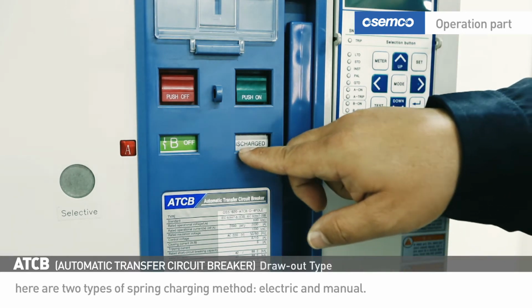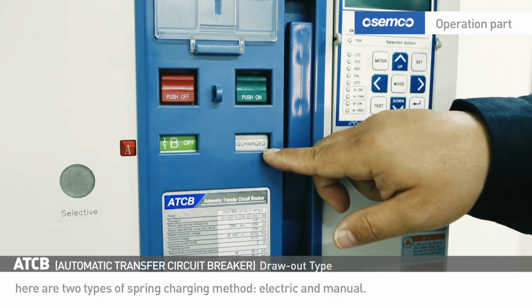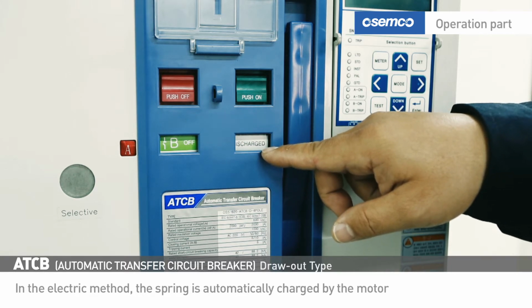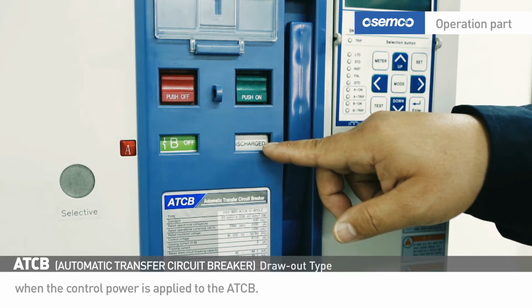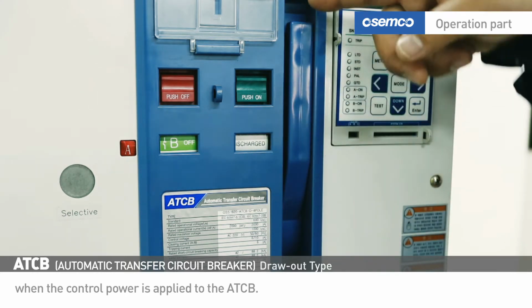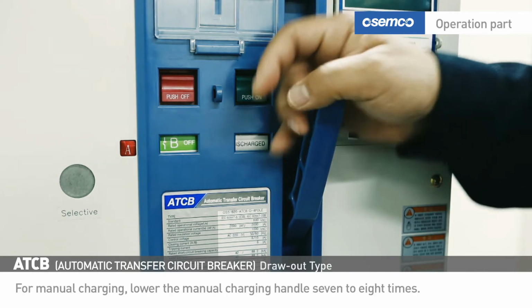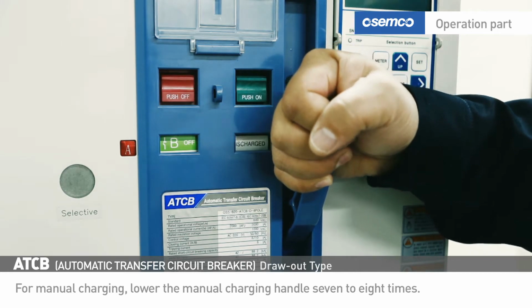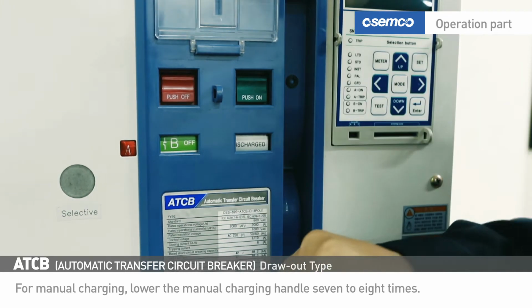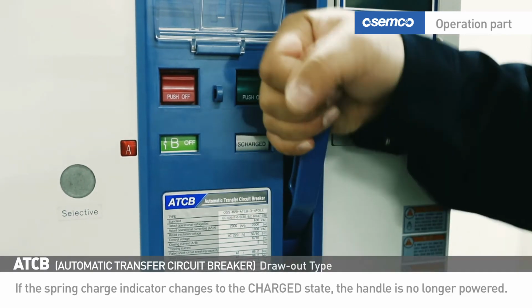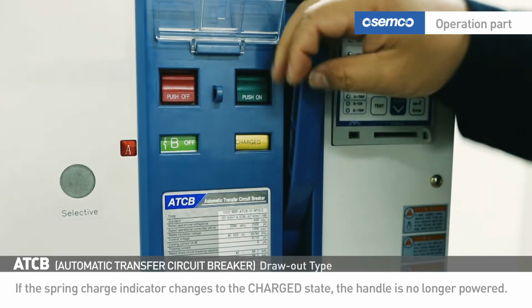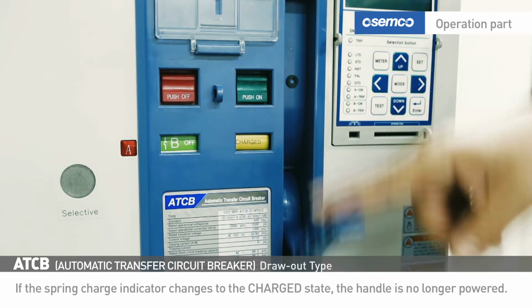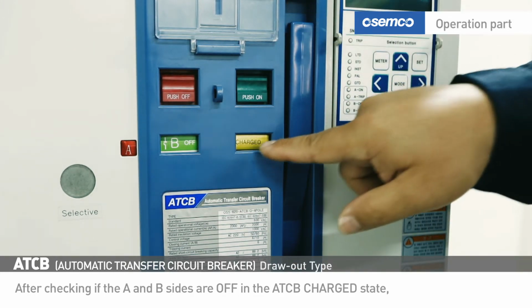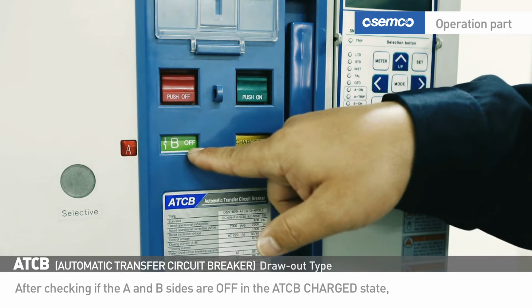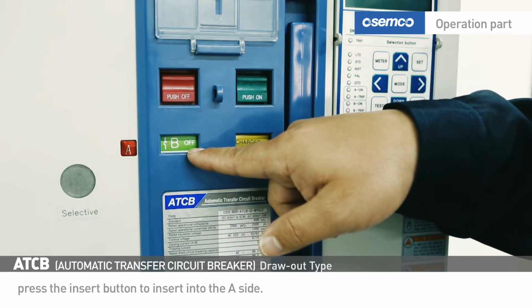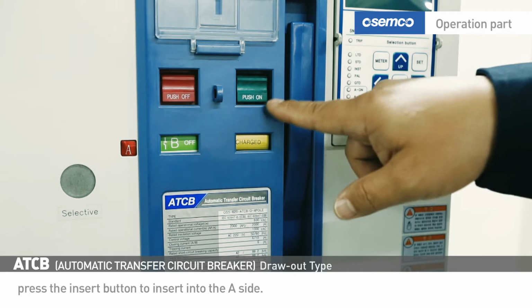There are two types of spring charging method, electric and manual. In the electric method, the spring is automatically charged by the motor when the control power is applied to the ATCB. For manual charging, lower the manual charging handle 7 to 8 times. If the spring charge indicator changes to the charged state, the handle is no longer powered. After checking if the A and B sides are off in the ATCB charged state, press the Insert button to insert into the A side.